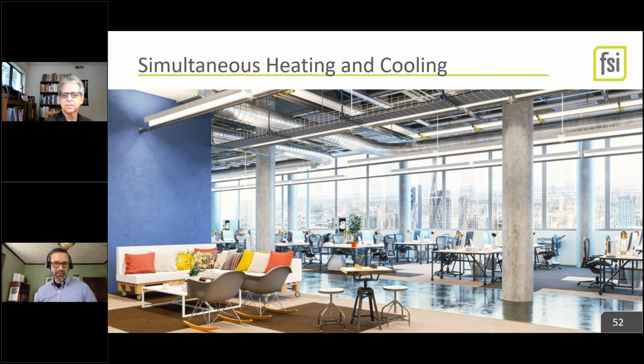At 40% window area, if you do a little perimeter heater on the radiator, you have fantastic comfort. Even without that radiator, as long as you're doing adequate airflow and washing those windows well, you don't really need that simultaneous heating and cooling as long as you're moving air around a good bit. So modern design, yes, we still draw it that way, and a lot of engineers just do it out of habit, but we don't really need to do this anymore, particularly in these long, skinny form factors we're now doing to get better daylighting and views and other less energy tangible effects out of our building.